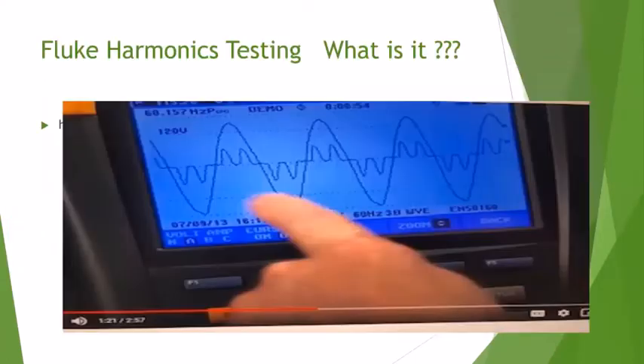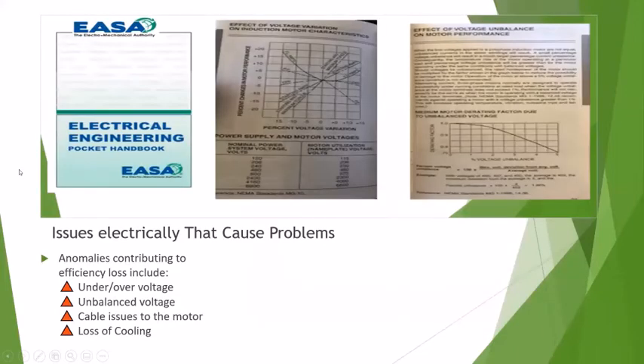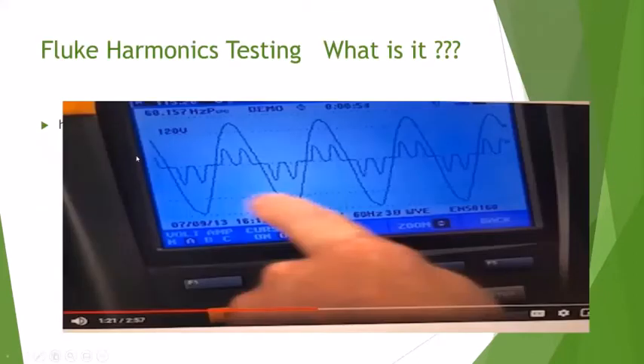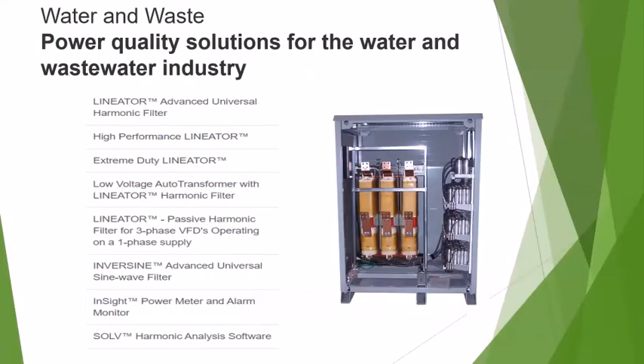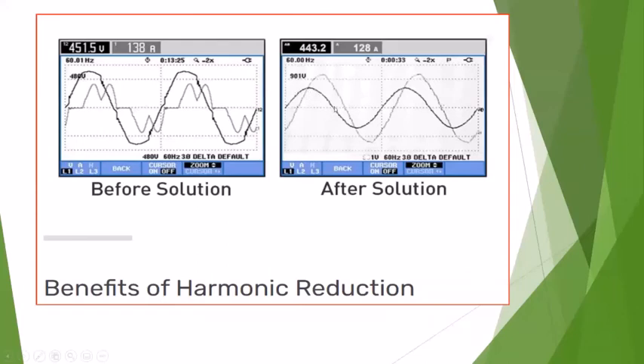Yeah, so what he's mentioning there is that when you put an extra transformer in and do a phase shift on those transformers, instead of providing three phases of input, we're actually providing six phases. So it tends to balance out these current waveforms because they draw current at various frequencies, and they kind of cancel each other, and that helps the main voltage form. We want to keep the voltage here as clean as possible, because otherwise this harmonic noise will also go into your heaters and other instruments in your facility. So harmonic mitigation is very important.